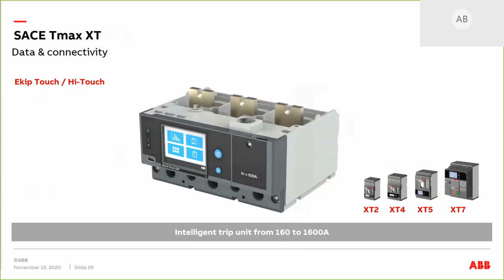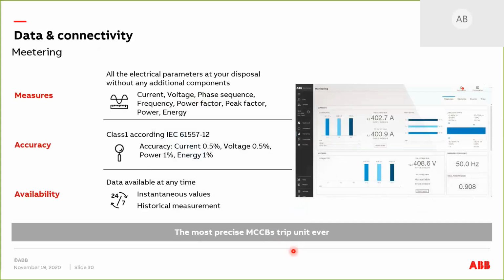When it comes to metering, you will be able to measure current, voltage, phase sequence, frequency, power factor, and peak factor. With the standard touch trip unit, you can measure up to this standard set. But if you have the High Touch, you will be able to measure everything here. All of these breaker measurements are actually class 1, for both the ACB and the MCCBs.